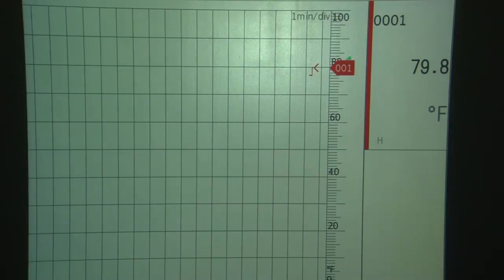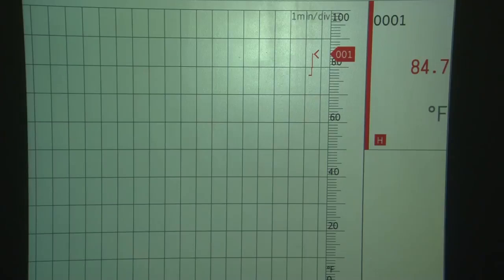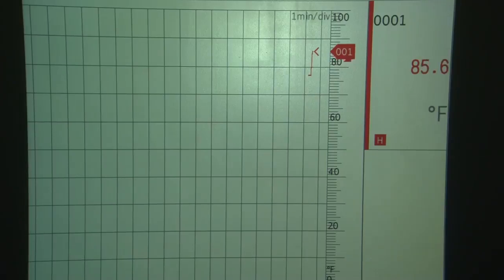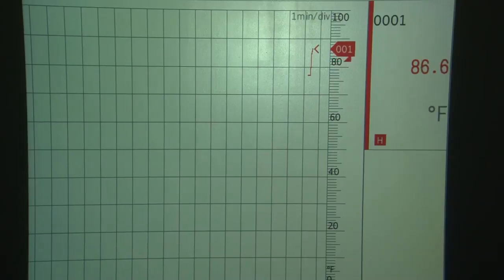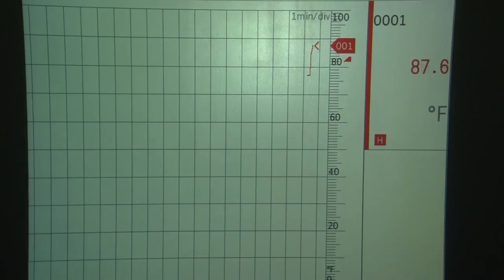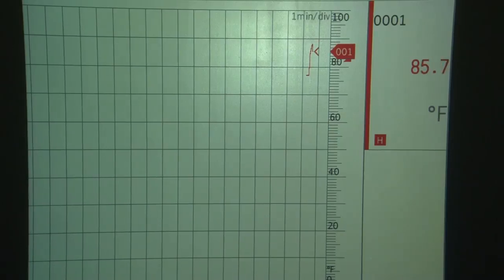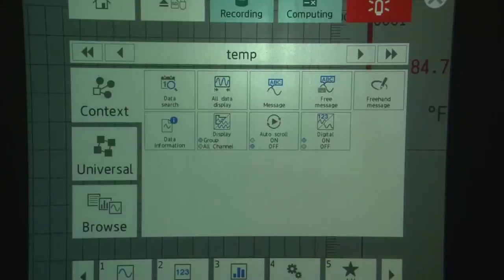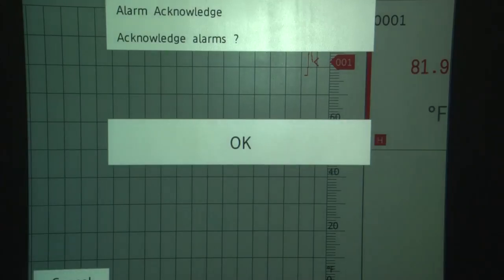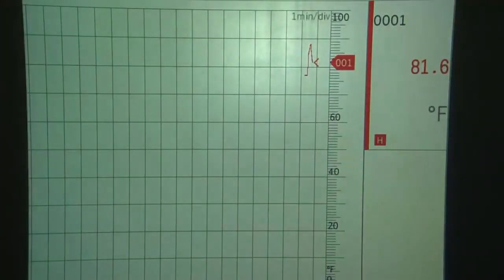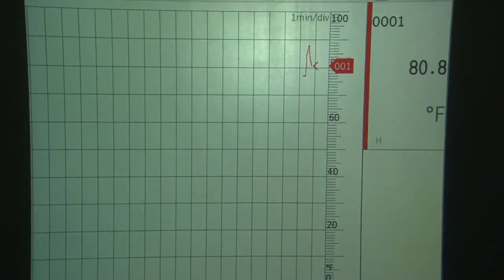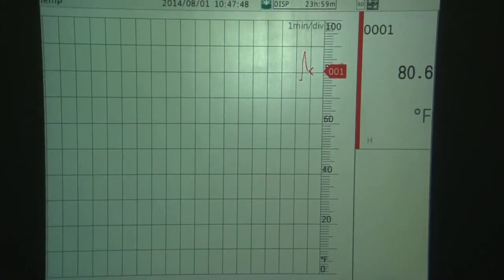We're going to grab the thermocouple. And we just exceeded our 82 degree set point. And we now have a high alarm on the system. If I touch the Menu key, I can acknowledge the alarm by touching the Alarm Acknowledge icon. Touch OK. And now that Acknowledge Act is recorded in the alarm log.